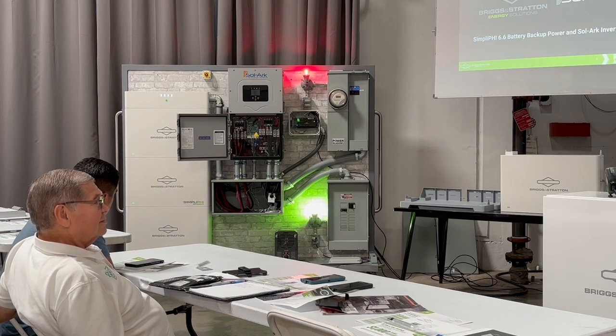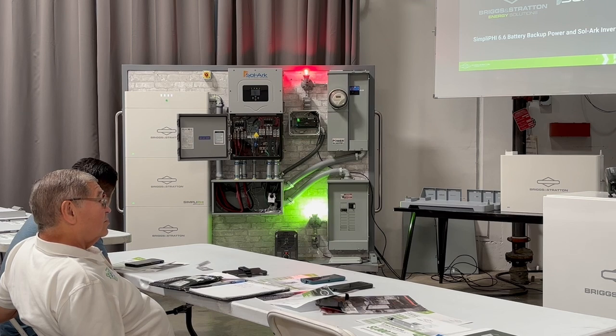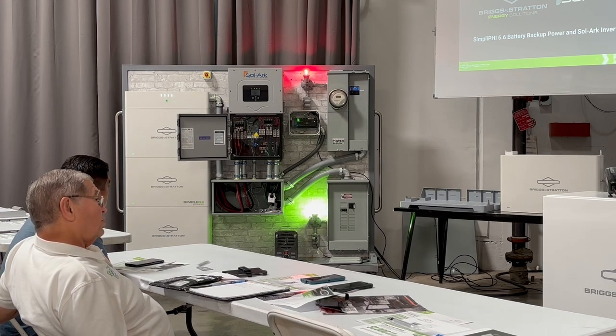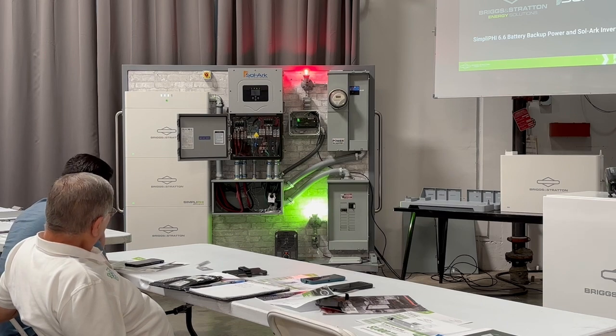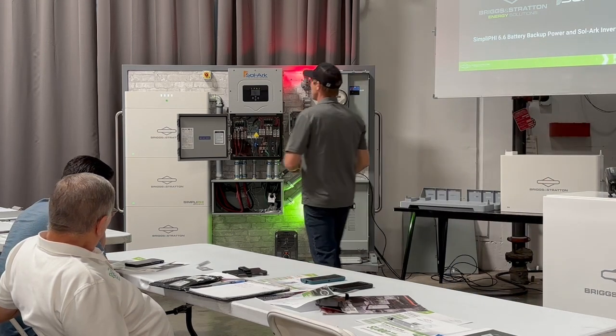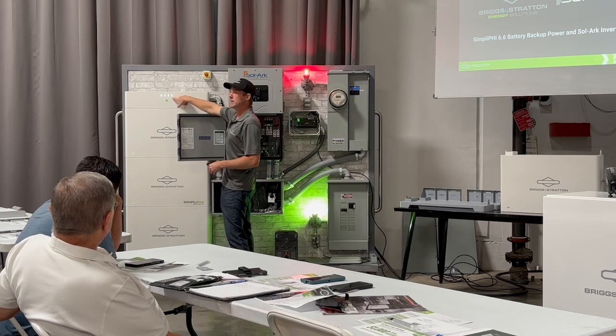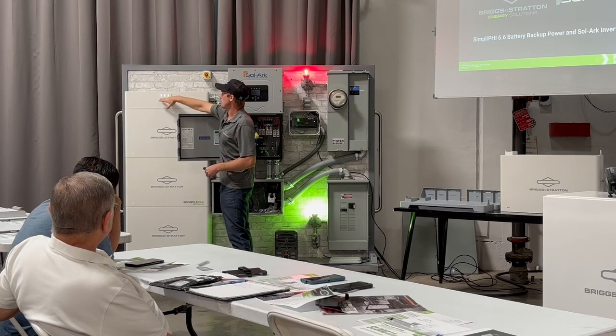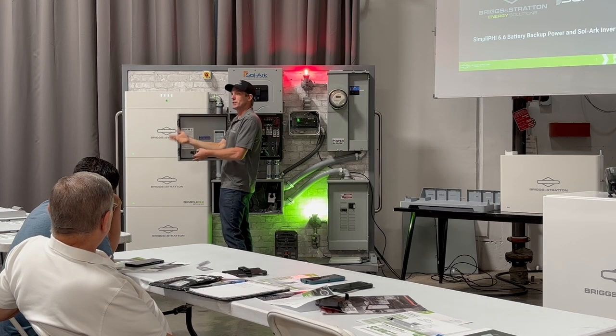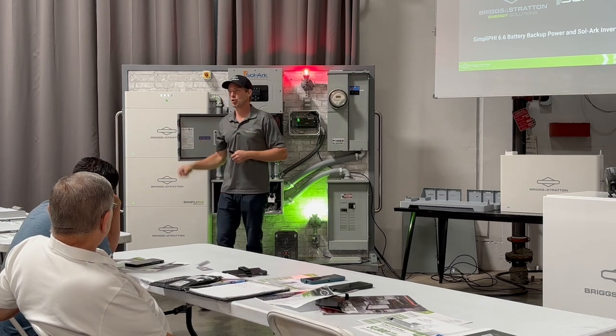So let me explain -- what you heard there was a click. What happened is I turned the utility connection back on, but it takes the Sol-Ark -- it's settable -- about 100 seconds to qualify that signal and make sure it's going to stay on before it starts passing it through. So while this was off and switching back on, the batteries were supplying the power. Let me point something else out -- this battery is probably going to be charged up fully, but it's blinking. When one of these indicator lights on the fuel gauge is blinking, that indicates the battery is in a state of charge.